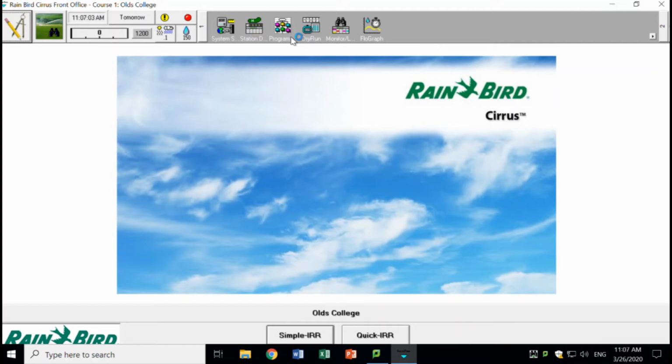In this video, we will be showing you how to set up a blowout program in the Rain Bird software. The parameters are you should not have more than 8 heads running at one time. This means only 4 stations at one time. This is due to our pump capacity. In this video, we will show you how to restrict your program into only running 4 stations at a time.